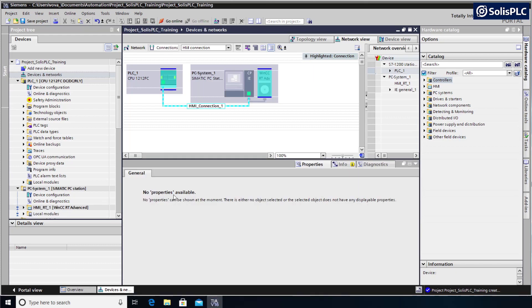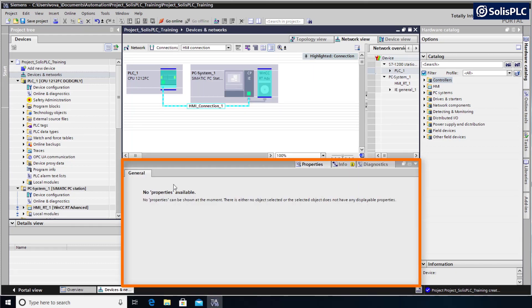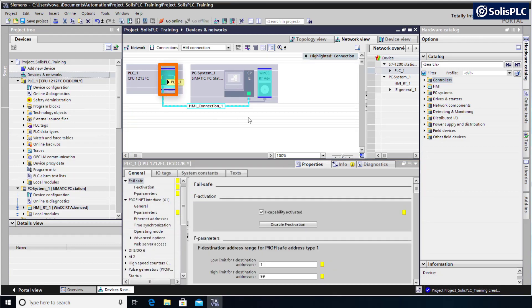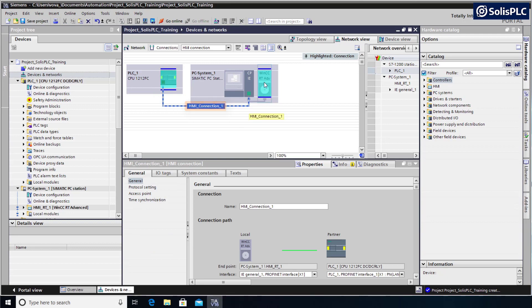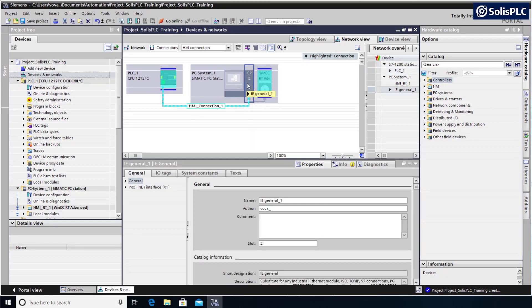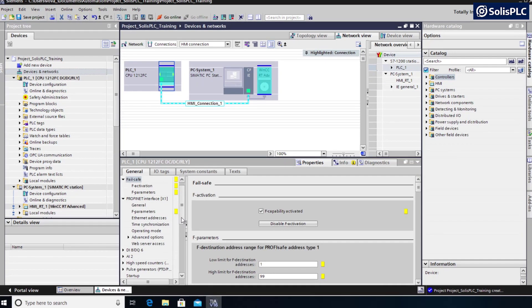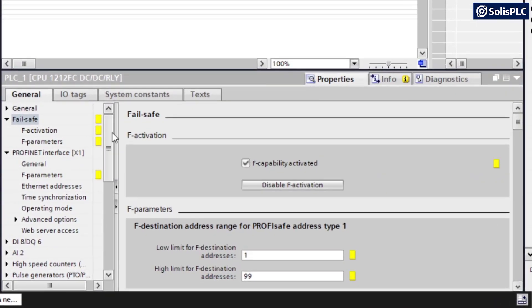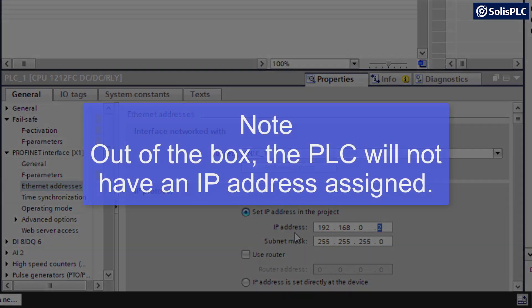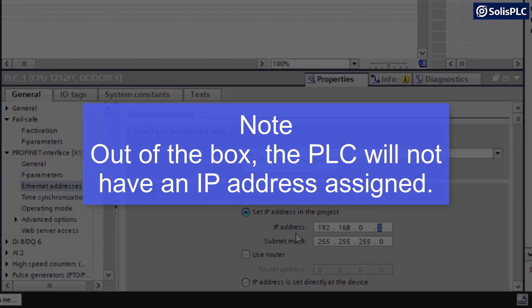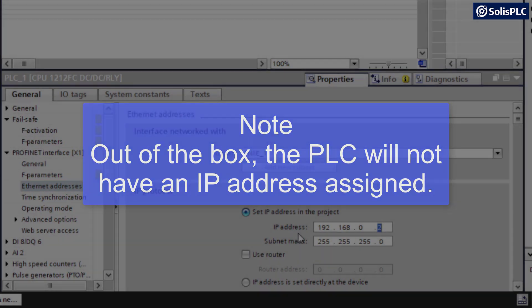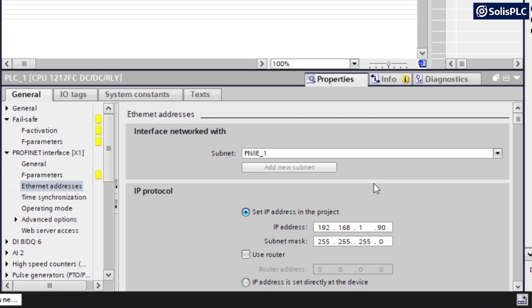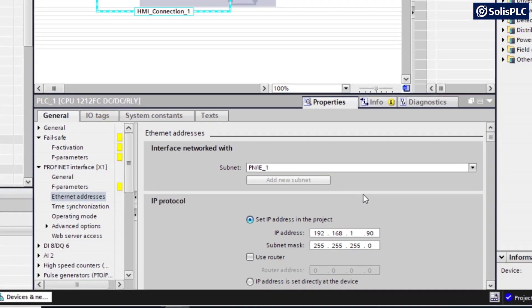The bottom panel in TIA Portal is going to be responsive to your selection. If you select the PLC versus the HMI Connection versus the Ethernet card in the backplane, you're going to see a different menu. Therefore, it's always very important to pay attention to what you've selected. Here we do want to select the PLC and we need to look at the Ethernet addresses. We need to set up the right IP address in order to be able to communicate with the physical device. In my case, that IP is going to be 192.168.1.90.